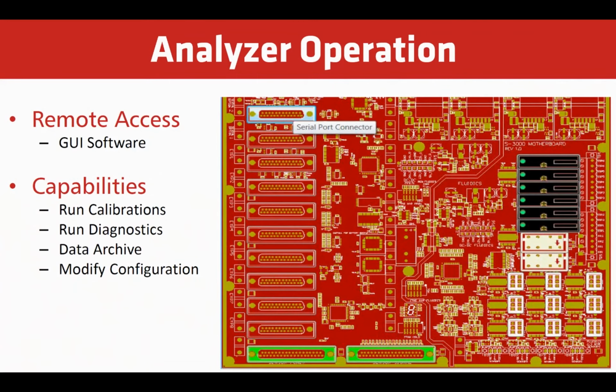We offer remote access through a remote GUI through Ethernet. And from this, you can do all of your run calibrations, run some diagnostics. You can archive the data or the results, or you can go in there and modify the configuration of your analyzer. For instance, if it was a 3-stream analyzer and stream 3 is down, you can simply go in remotely and disable stream 3 so it only runs 1 and 2. So it's used for those types of scenarios.